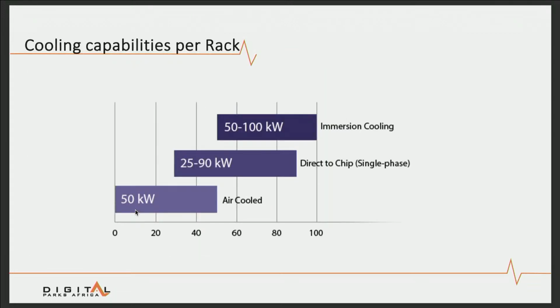Here's just a quick overview on the different forms of cooling. So the different temperature bands essentially overlap, but what we are finding round about the midpoint of each of these temperature ranges, these different technologies really hit the limit of what cooling they can provide. Immersion cooling has already even run up to 200 kilowatt per rack, but it's still an emerging technology itself. So at the moment, the recommendation is up to 100 kilowatt per rack on immersion-based systems.